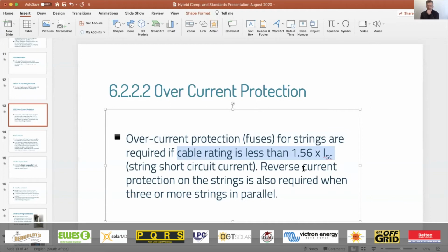So overcurrent protection is required for strings when the cable rating is less than 1.56 times the short circuit current. Yeah, I needed to repeat that because sometimes these sentences are written in a way where you've almost got to reverse engineer what you are reading. So what they are saying is if your cables can handle the short circuit current, then you don't have to fit fuses.